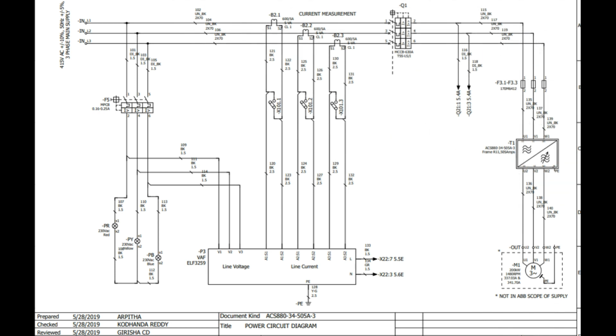After the single line diagram, next we'll come to the power circuit diagram. We'll start from the left hand side again, and here you can see the three phase supply. It's again 415 volt plus minus 10%, 50 Hz and so on. And the very first tapping that we saw in the single line diagram is F5, that is MPCB, and this tapping is for indicating lamps.